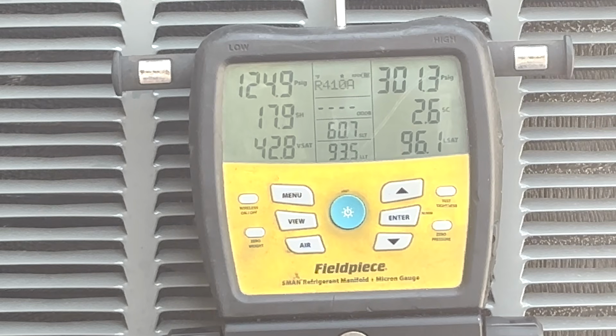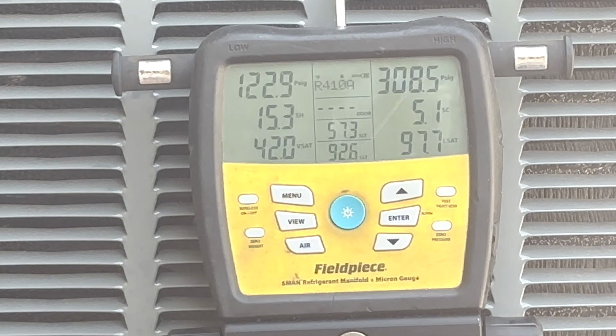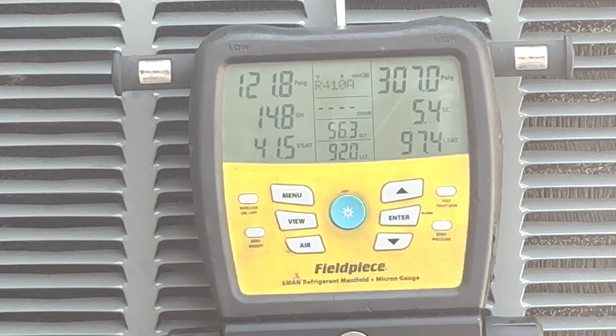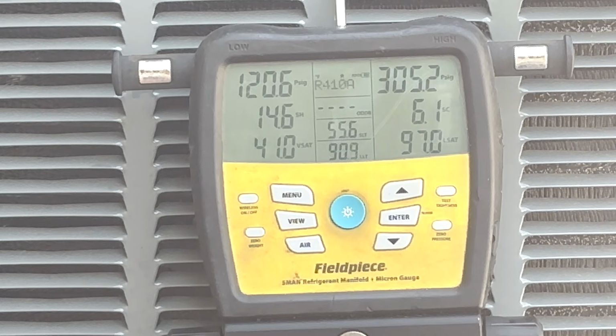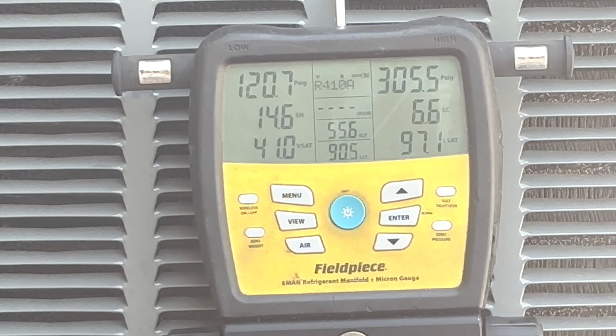What will give you wrong data is non-condensables, which could be moisture, it could be air, it could be anything that was introduced to the system during the installation, or if not during the installation, maybe during service. Right? People not putting their gauges on properly and purging those hoses out. They could easily add other refrigerants to it, an ounce at a time, or even some moisture. And so once those integrate into the system and the compressor is moving that gas with those non-condensables, then we're going to get wacky pressures and wacky superheat and subcool values that we can never compute.